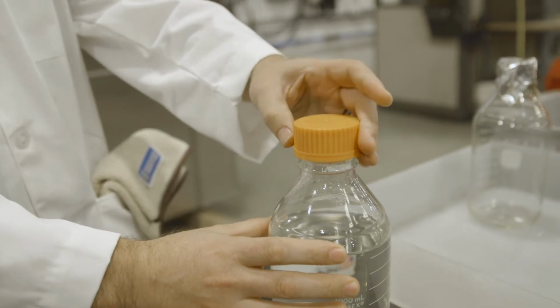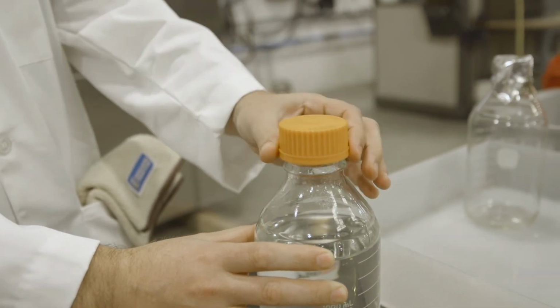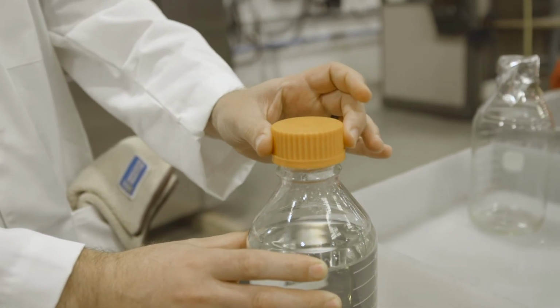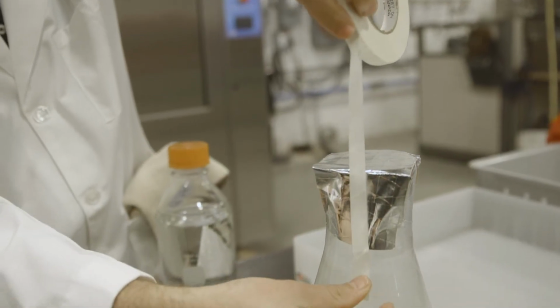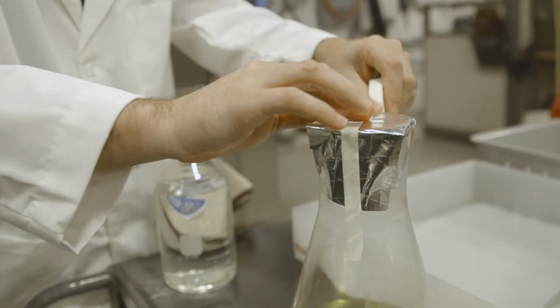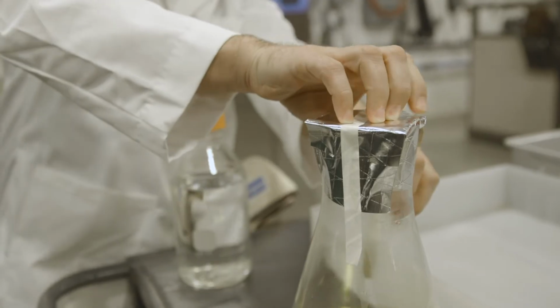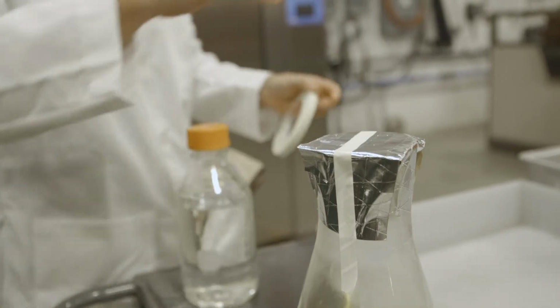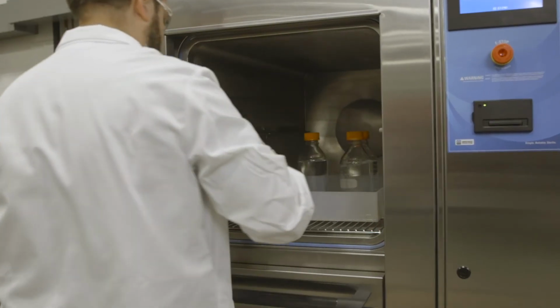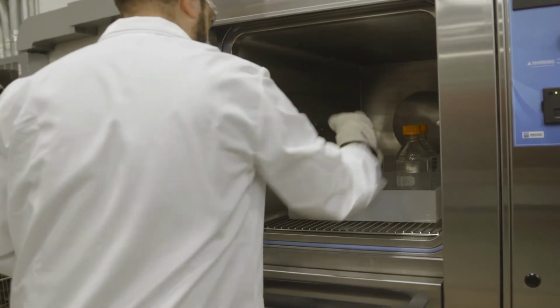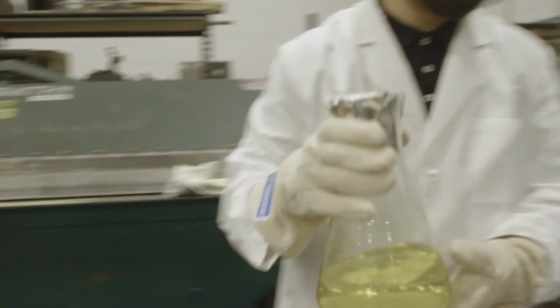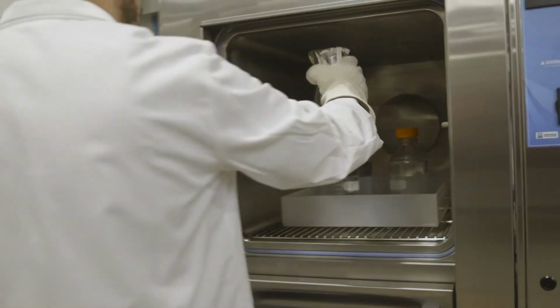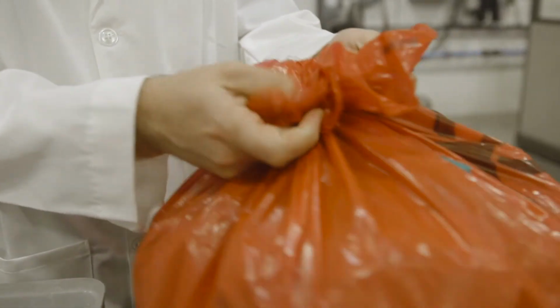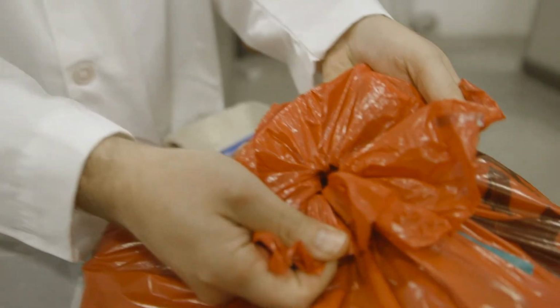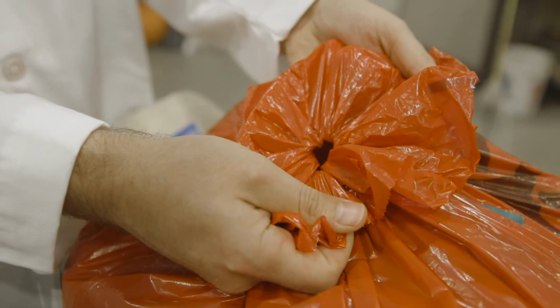On glassware with lids, be sure to loosen the lids so that the steam can penetrate inside. For glassware without lids, like beakers, wrap the top with aluminum foil. Some people will place autoclave tape over the foil, which changes color after a successful cycle. Place glassware containing liquid in a secondary containment pan made of autoclave-safe materials. Red bags should not be tied shut or otherwise sealed. There should be a slight opening in the top of the bag to allow steam to penetrate and escape.